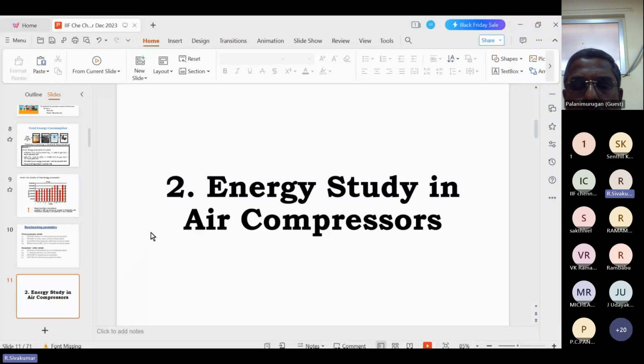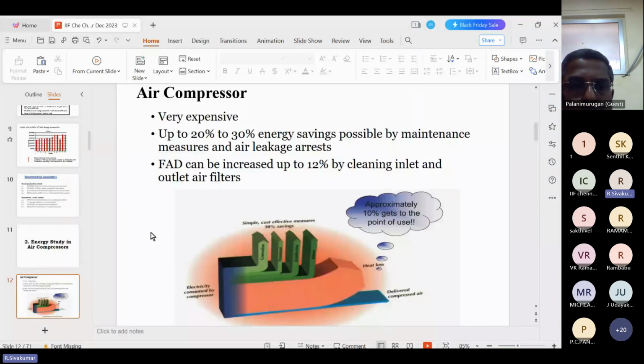The second thing is the energy study in air compressors, because air compressors are used in mostly all foundry units. During the energy audit, what are the points we measure in the air compressor? Here is the Sankey diagram. The Sankey diagram shows the input and the output, how much energy was usefully converted to air, and the remainder is converted to loss. The small blue layer at the bottom of the Sankey diagram is the delivered compressed air. That means hardly 10% of the input energy is converted into compressed air.